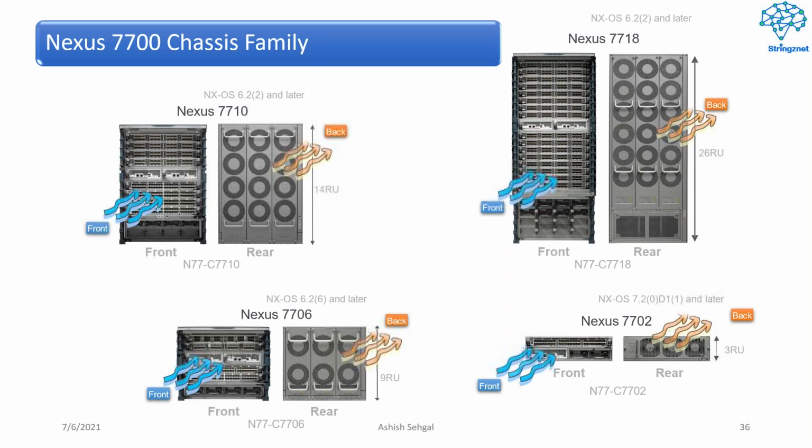It was just in the 7000 series that Cisco introduced the glass doors and the discrete airflow, which definitely impacts the performance of the switches. If you put the glass doors, more heat will be generated, and cooling efficiency will be impacted. Right.